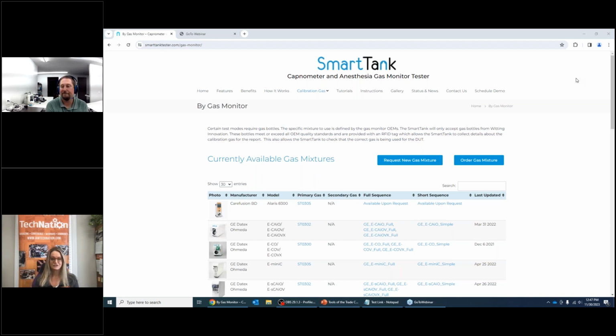Keeping OEMs in mind, do you have manufacturer approval to use these devices on their monitors? We've talked to a number of them and they're aware of it. They don't typically endorse products. Sometimes they'll reference a flow meter, but then they always say, use this flow meter or something equivalent. So they don't tend to care as long as you're doing it correctly. They don't make money off the PMs, unless you send it to them and they're contracted, that's another story. But they don't really make money on you doing the PMs and selling you equipment. As far as the gas goes, it's all certified gas from a gas manufacturer. It's made to the same standards that any of the other gas is made to.